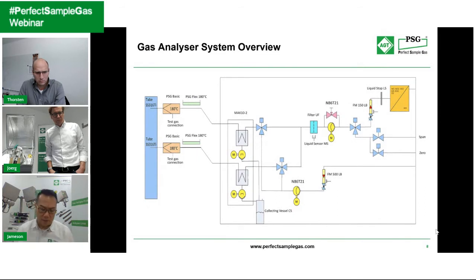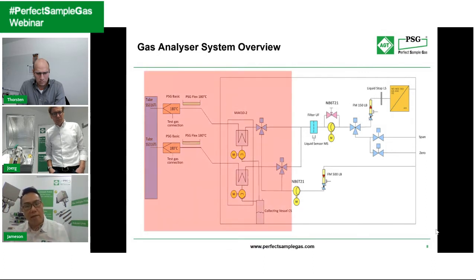So, what I say today is we are not going to talk about every sampling component. These are two areas which I want you to take a very serious look at. Whenever you configure a CEMS system, number one, make sure that from the sample probe to the gas cooler, it is above the acid dew point. All right, it must be above the acid dew point. Otherwise, you will start to have corrosion, blockages, and losses of gases.